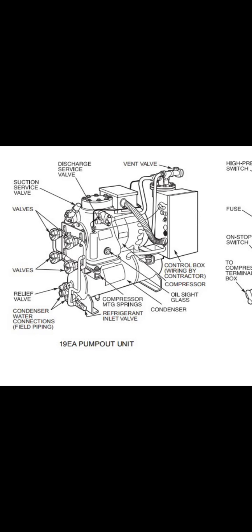This is a 19EA pump out unit from Carrier. It is standard, you can find it on centrifugal chillers. The pump out and pump down procedures are totally different. As per my knowledge, some chillers have a program and they use the word pump down. Pump down means when they shut down, they have to pump down. This is the normal procedure: they close the solenoid, pump down, and then shut down. This is normal for shutdown.